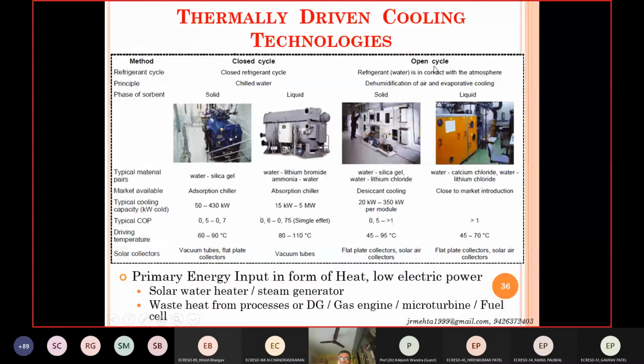And in the open cycle systems, you can either adopt desiccant cooling, solid desiccant or liquid desiccant. But actually, solid desiccant and liquid desiccant systems are mainly for latent load removal. You can convert a part of it into sensible cooling, and you can utilize other types of sinks for removal of sensible heat that need to be combined with this, but they are mainly for the purpose of latent heat removal. You have to combine another source, or rather sink, to take away the sensible portion of the heat. Okay.